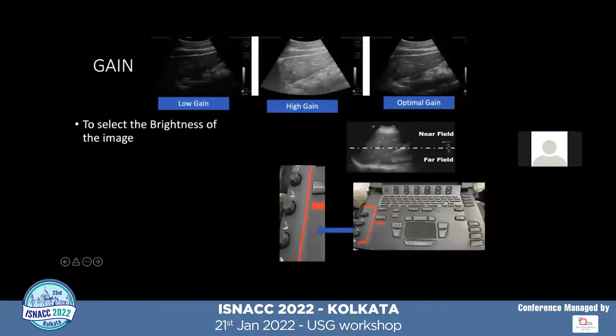And when you use the manual knobs, the upper one controls the gain of the near field only, the top half of the screen, and the middle one adjusts the gain of the lower half of the image, that is the far field, and the lowest one you adjust manually, the gain of the whole image.